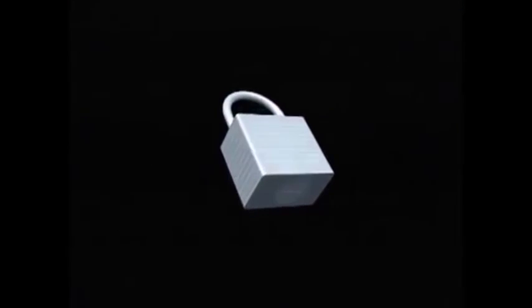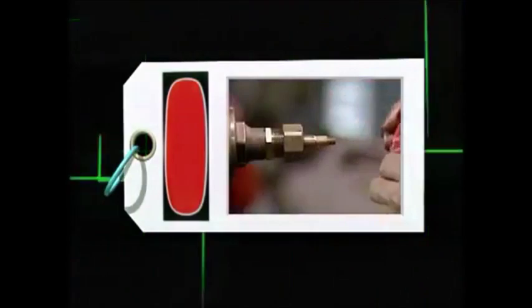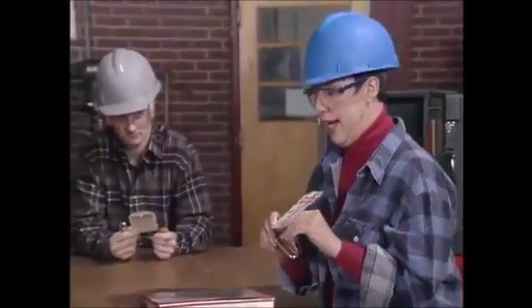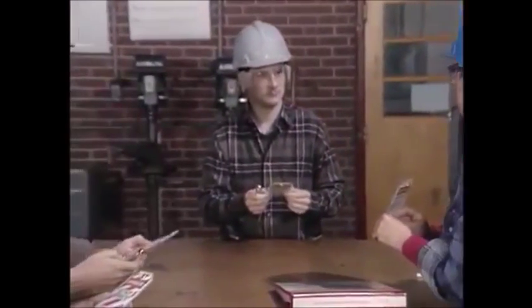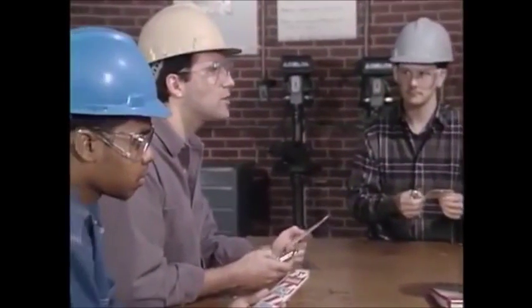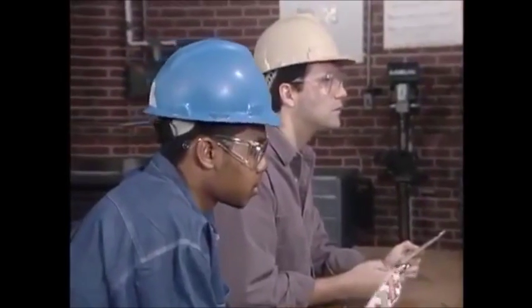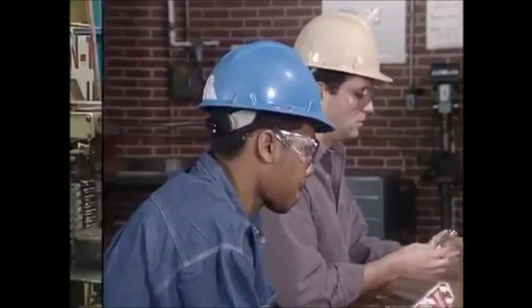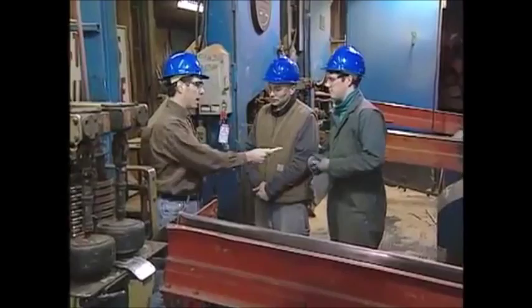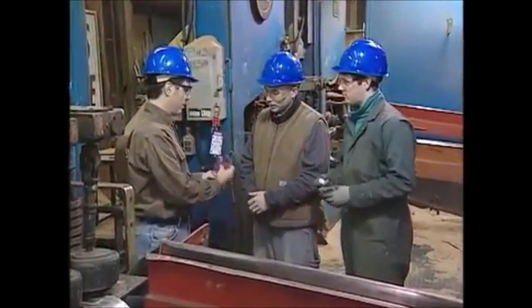OSHA considers using a lock safer than just using a tag, and most companies require both lockout and tag-out. If only tags are used, extra steps must be taken to prevent the energizing of machinery, such as removing a valve handle or blocking a controlling switch. Employees should be trained in the limitations of the tag-out system. It's very important to obey the warnings on tags, especially since they will not physically keep you from turning power on. Your employer will provide all lockout tag-out materials needed.